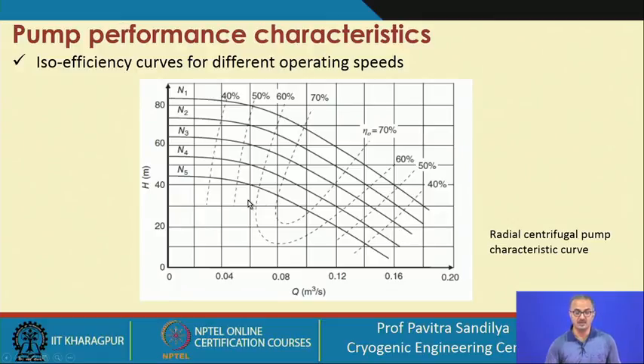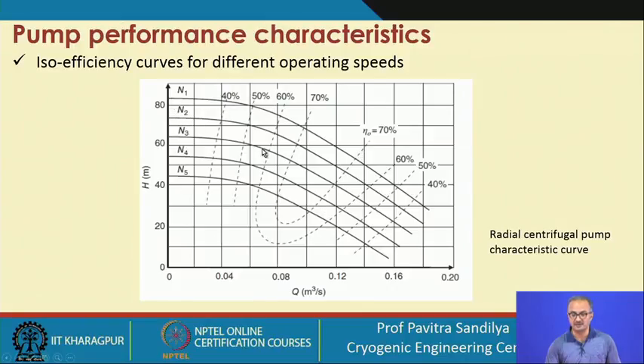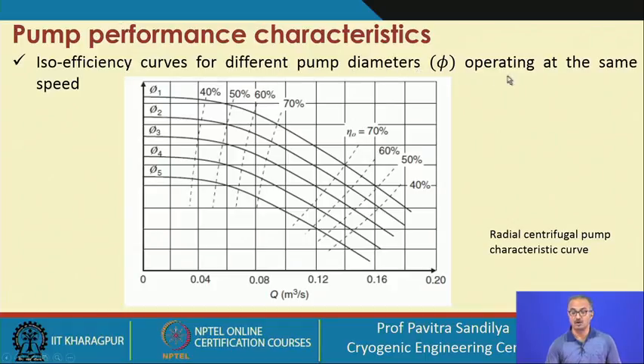Here we have another presentation — isoefficiency curves for different operating speeds. We again plot head versus flow rate, but now for different operating speeds. The contours labeled 40%, 50%, etc. represent lines of the same (iso) efficiency, drawn for different flow rates — also for a centrifugal pump. Similarly, isoefficiency curves for different pump diameters operating at the same speed are plotted with various efficiency contours. We shall see later how to use these characteristic curves in determining the performance of a pump.